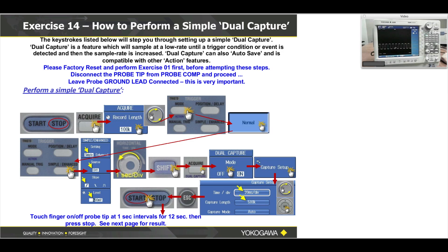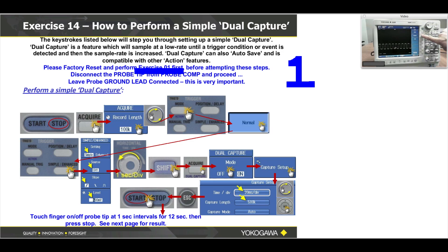I've given you an exercise here of how to perform a dual capture. I would encourage you to do this — it uses one probe, so one channel. It can be a tricky exercise, but I'll do it on the screen here. Let's all go back and do exercise one. I have the probe connected to the compensation signal. I'm going to hit setup, then press auto setup. So I've got about two cycles — let's all attempt dual capture.